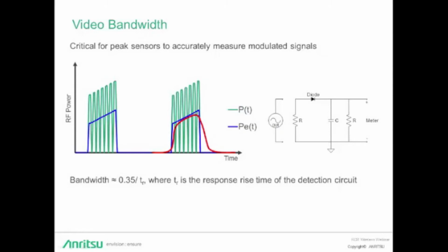Now there is a trade-off for making the sensor faster or increasing the bandwidth. Going back to the low-pass filter analogy, while a higher pass band enables the sensor to respond to higher frequency signal changes, the additional responsiveness makes it more sensitive to noise. So this is going to reduce the range of the sensor. A sensor that may be able to measure average power with a high accuracy at minus 60 dBm may only be able to get the same accuracy at minus 20 dBm when utilizing the full bandwidth.